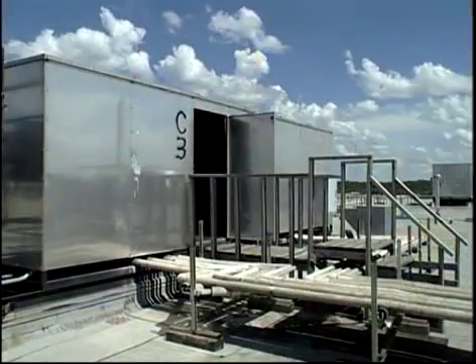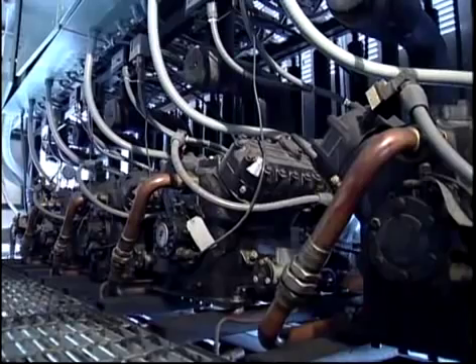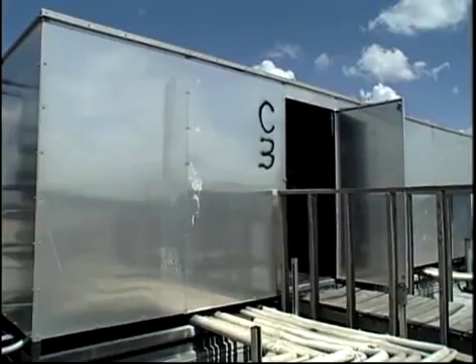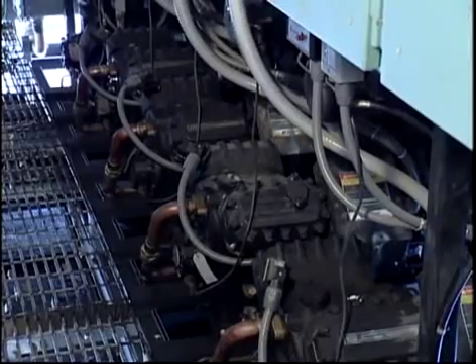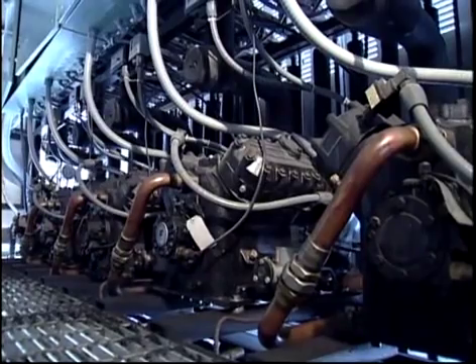The compressors are grouped together in these rack shacks for convenience, safety, economy, protection from the weather, and in general, a more technician-friendly environment. These compressors have all been retrofitted to use the more environmentally friendly HFC-R507 coolant instead of the ozone-depleting CFC-R502. All of these units are 460-volt, three-phase reciprocating compressors.